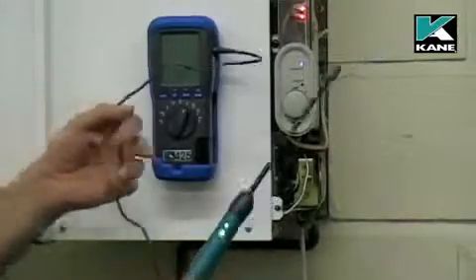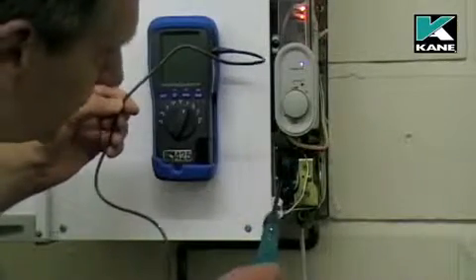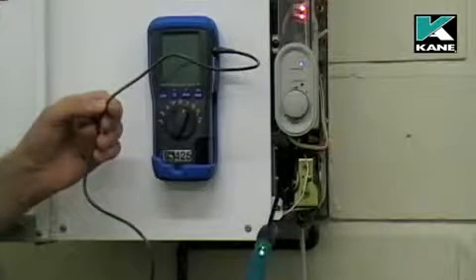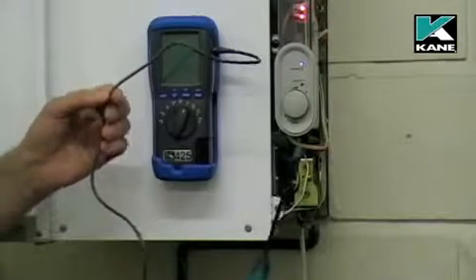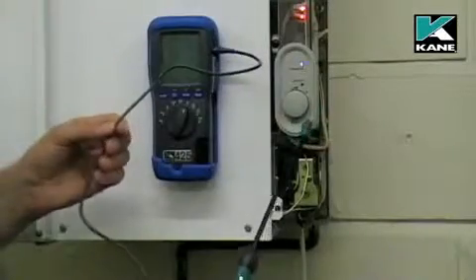If we now move the head of the gas leak detector to the test point, we can see there's no speeding up. Therefore, the test point is gas-tight.